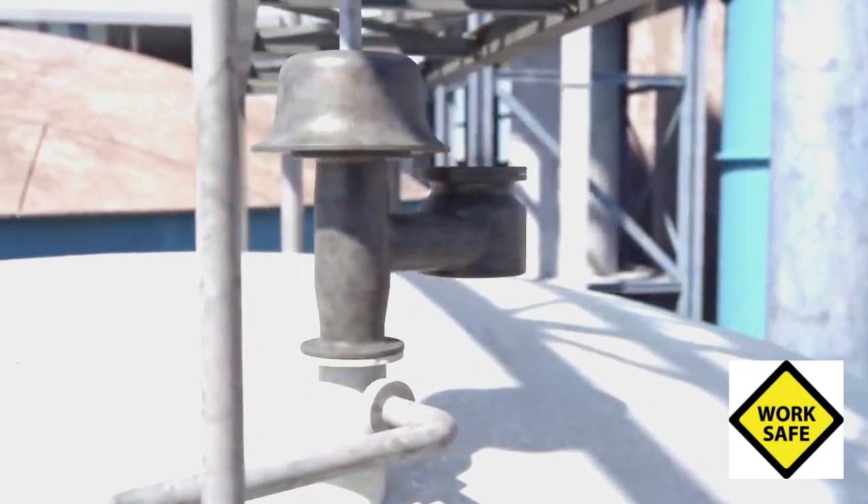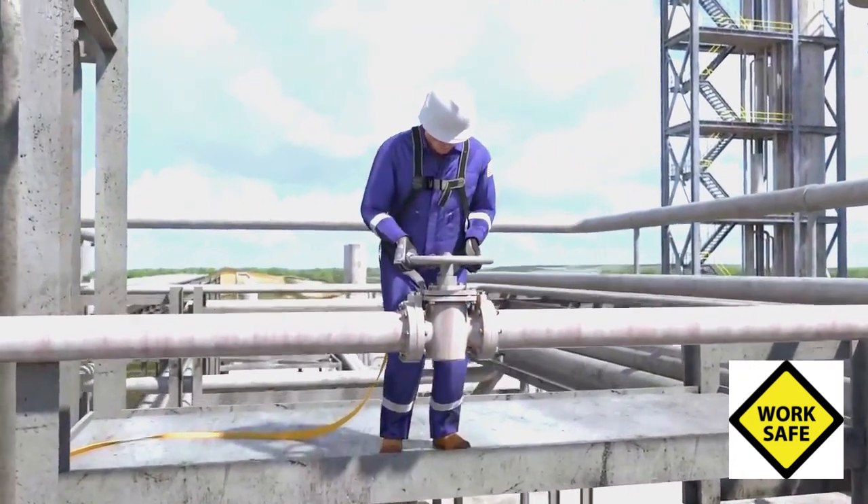The low pressure most likely triggered a relief valve on the tank's roof to add more air to avoid damaging the tank from a vacuum. The vacuum relief valve was likely one of the few potential sources that allowed enough air into the tank to create an explosive atmosphere. The day before the incident, in preparation for repair, the water piping was isolated from the foul condensate tank by closed valves and physically separated from the tank.